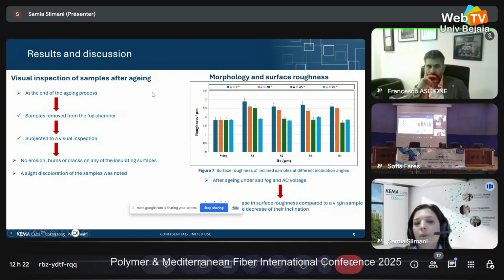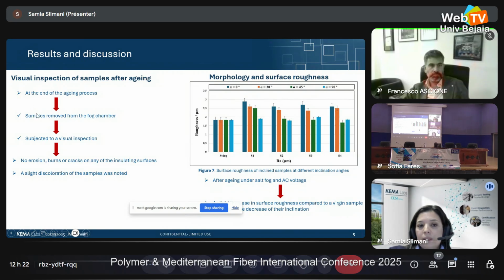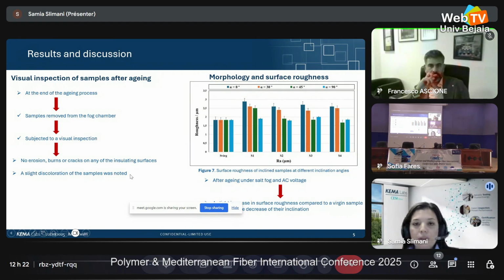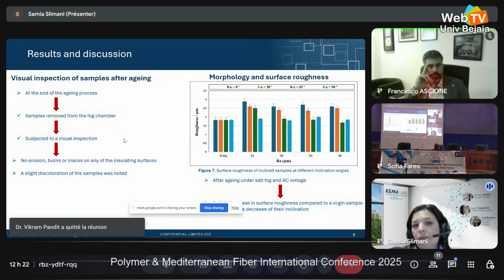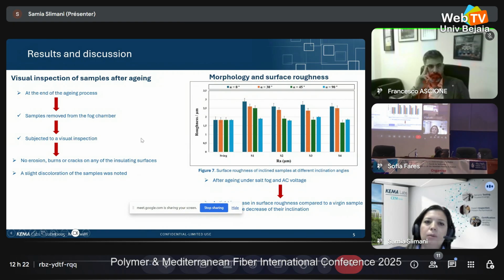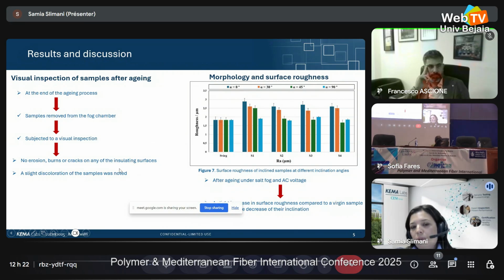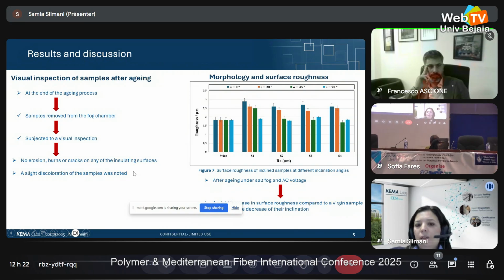At the end of aging, the samples were removed from the fog chamber, and visual inspection was done on all samples. The result: no burns, no tracks, no erosion was remarked on all samples. However, just slight discoloration was remarked on all of the samples, regardless of inclination angle.